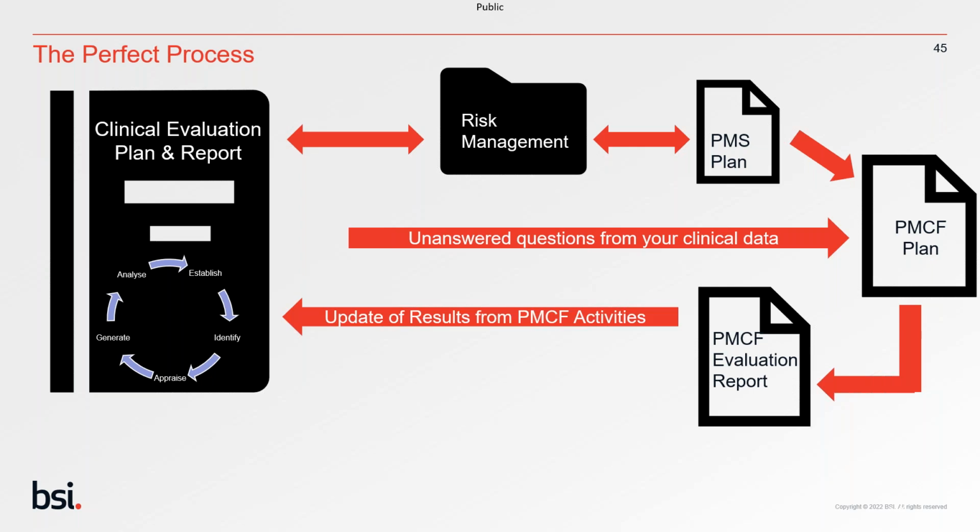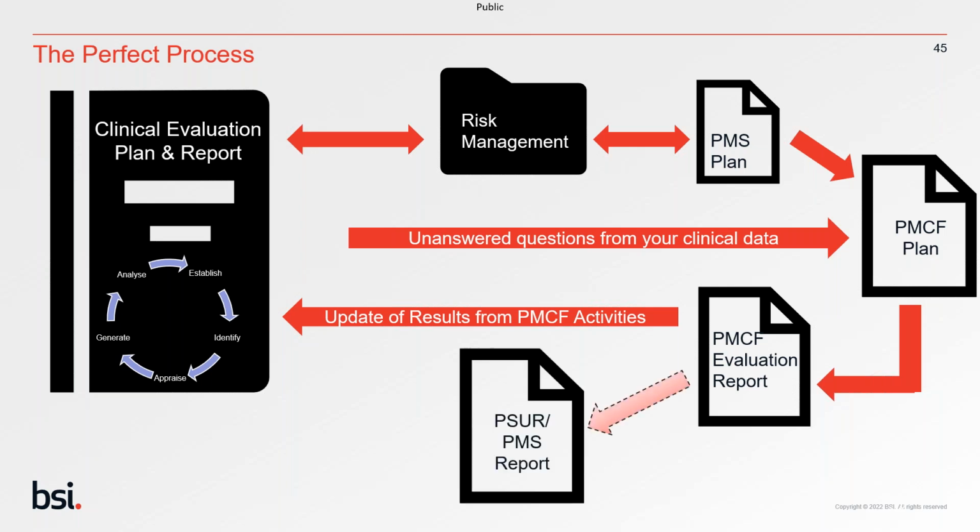Stay with me. And those updates of results from the PMCF activities feed back into your clinical evaluation plan and reports. So really, whatever you've conducted, the information you identified needs to go back into your clinical evaluation plan and be considered as a whole. But also your PMCF evaluation report needs to feed into your periodic safety update report, or your PMS report if you're a class 1 device.